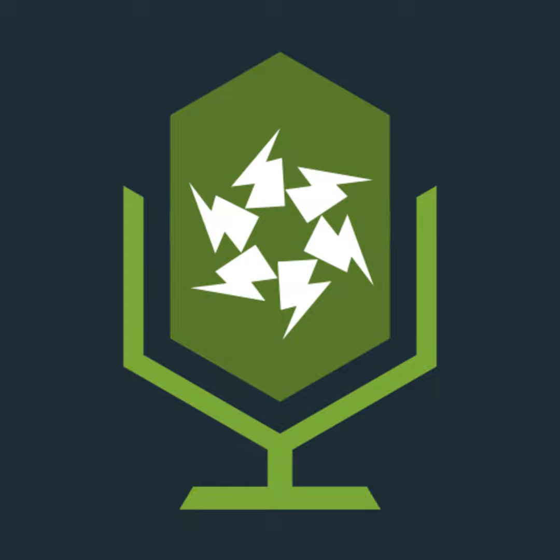And then we have this table, minimum cross-sectional area of conductors, and it just tells us minimum size for lighting circuits, copper 1 mm, aluminium 16 mm. Now, whilst there is a resistivity difference here, this is mainly due to the material's mechanical strength. Aluminium is a much softer conductor, and so it's sized larger for mechanical strength. That's quite often the reason why aluminium is used. It's light and soft, but we need larger cables due to that strength.